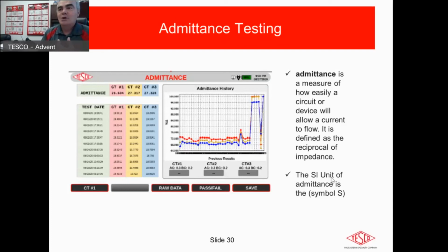Because sometimes you can have locations that have a dozen or 18 different metering sites there. And are you at site number 5 or site number 6? So opening up the cabinet and seeing exactly what's in the picture helps you feel comfortable that, A, I'm at the right place, and B, nobody's been screwing around with it because it looks the same as when the last technician was out here 2 years ago. Admittance is very much the same thing. An admittance test all by itself means nothing. However, if someone did an admittance test 2 years ago and I come out and do an admittance test and we get the same result, I can feel really good that nothing has changed in that circuit.